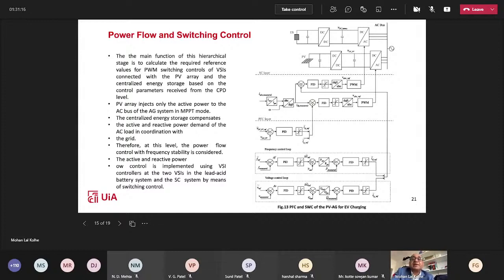Then active and reactive power demand of the AC load in coordination with the grid. Therefore, the power flow control with frequency stability has to be considered. If we don't have only the real power load, but also active P and reactive Q load, then we have to use the reactive power droop characteristic functionality also. This droop characteristic is especially used in the battery and supercapacitor units, where we can use the frequency control loop.